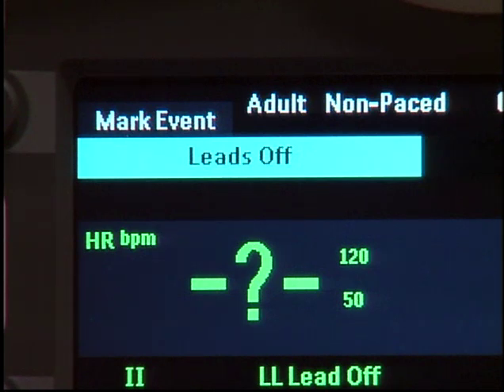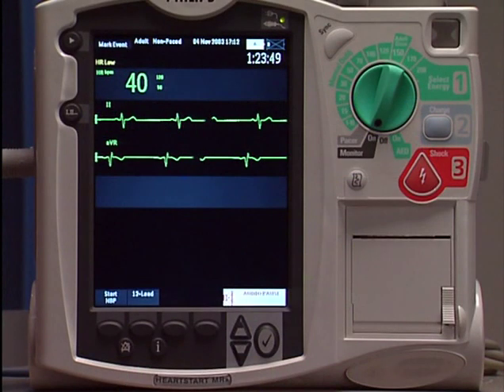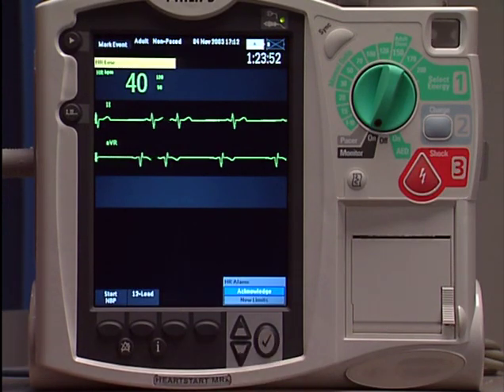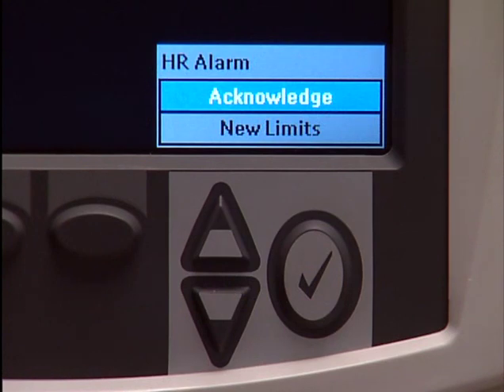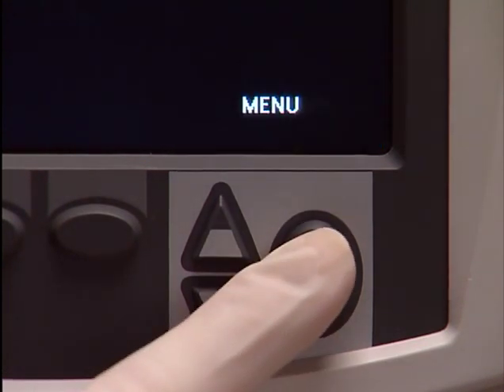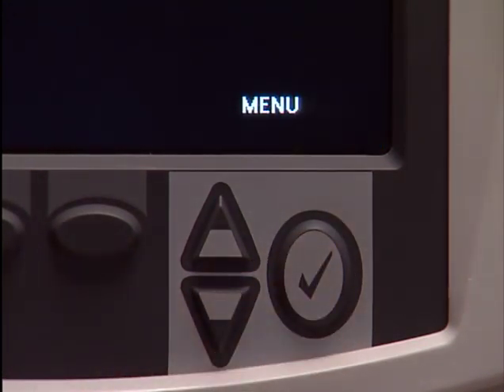Inops indicate a device problem or error condition, such as this leads off message, and they appear in this cyan background and sound like this. To silence active alerts, you use the menu select or the navigation buttons. Once the condition is corrected, press the menu select button to acknowledge the alarm.